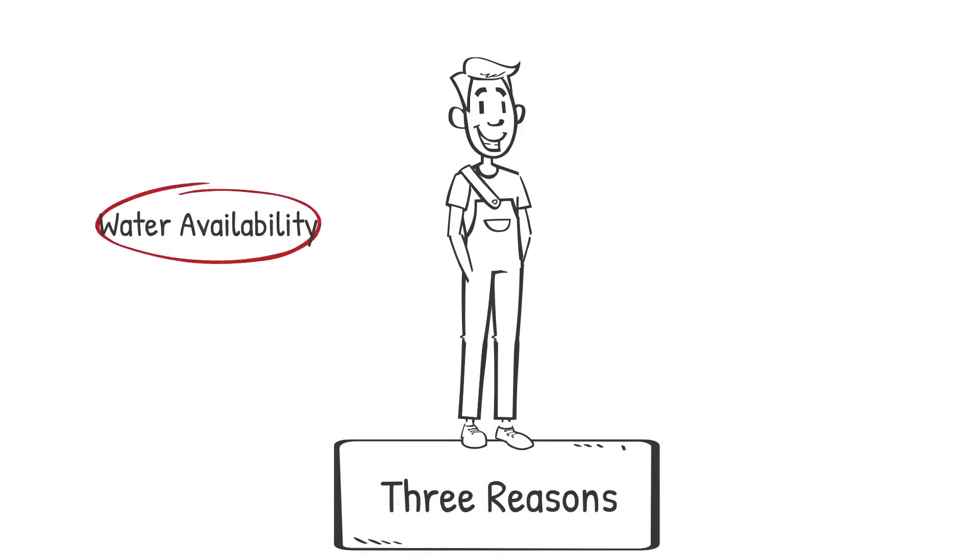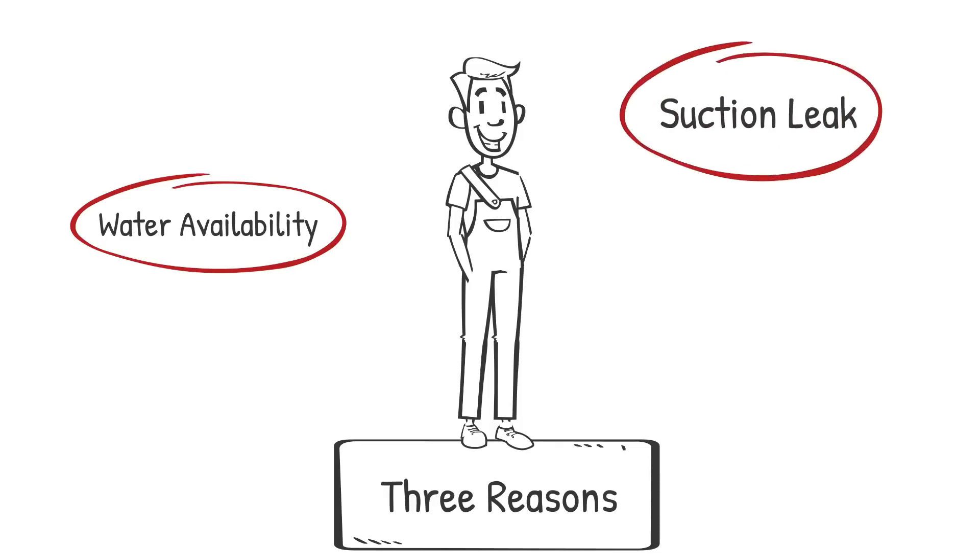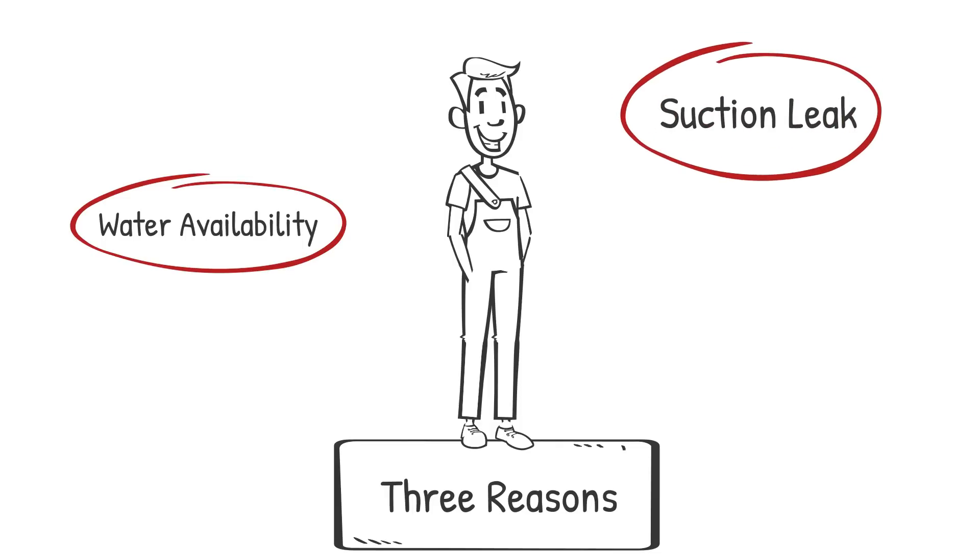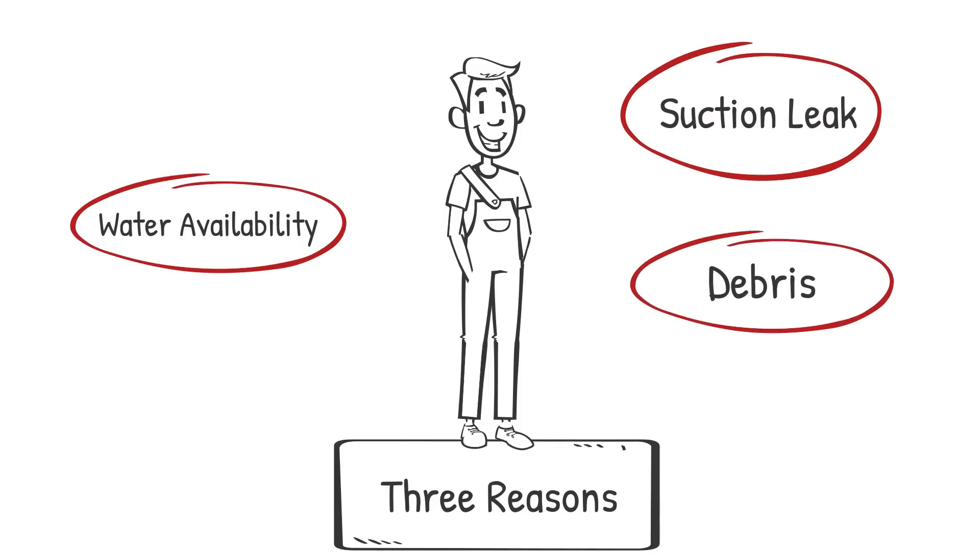One, there is no water available from the water supply. And two, the suction assembly has an air leak. And three, debris is caught at the foot valve filter and or your strainer.